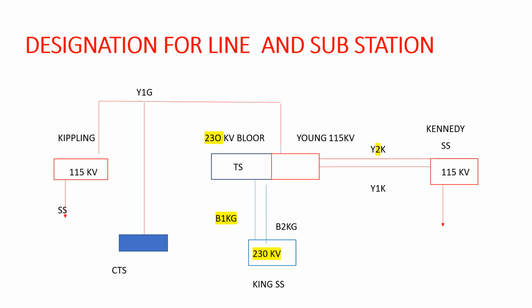So three types of stations you will usually see in the network, maybe in Ontario, Toronto, Alberta or anywhere: CTS, TS and SS. What is SS? SS is a switching station, where you are only switching the lines from one station to another; the voltage level is not being changed. So these stations will be known as switching stations. The line will be going away from here, but with the same red lines. Here I have shown in blue the 230 kV lines, and in red the 115 kV lines.